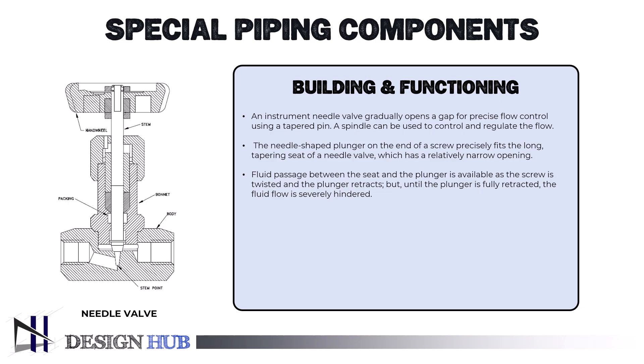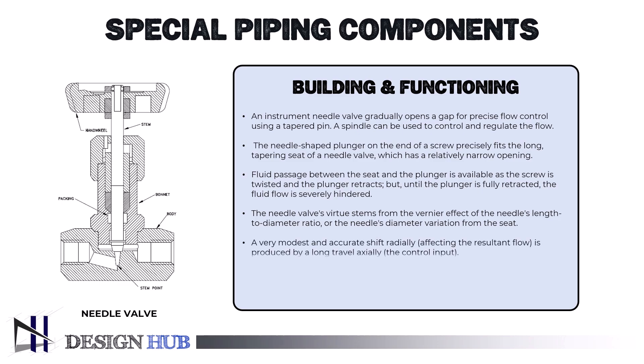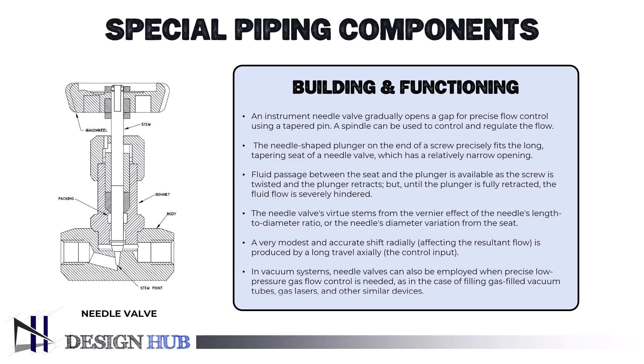Precise control over the flow rate is readily achievable because retracting the plunger requires numerous turns of the fine-threaded screw. The needle valve's virtue stems from the vernier effect of the needle's length-to-diameter ratio. A very modest and accurate shift radially, affecting the resultant flow, is produced by a long travel axially, the control input. In vacuum systems, needle valves can also be employed when precise low-pressure gas flow control is needed, as in the case of filling gas-filled vacuum tubes, gas lasers, and other similar devices.